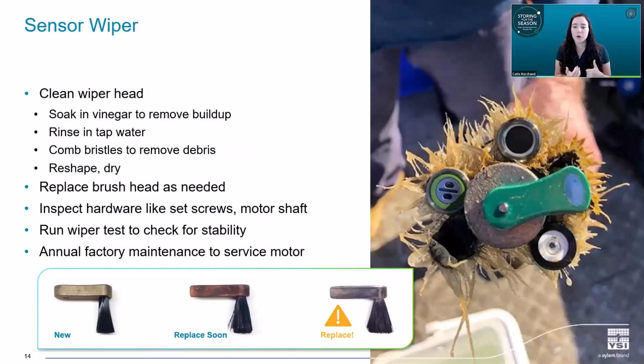And then a lot of deployable water quality instruments have wipers that help keep the sensor faces clean, especially if they're in the water for extended periods. For example, the EXO sonde has a central wiper, and it's really powerful, but it definitely benefits from regular care. And it definitely should also be maintained before you put it into storage. So be sure to clean the wiper body and the brush head. You can rinse the brush in clean water and comb out any debris you might see in the bristles. And if algae or scum is really built up in there, you can soak it in white vinegar to help dissolve it, then rinse it off with clean water, squeeze out the excess on the brush, and then let it dry.